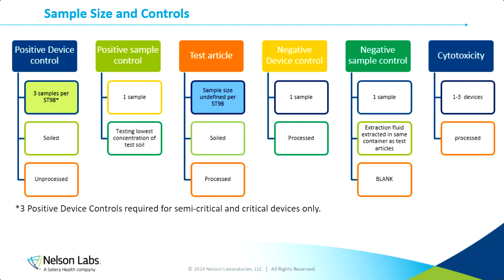The next topic or change is surrounding sample size and controls. These are all the necessary controls of a cleaning validation. We have the positive device control, and in ST98 they want to see 3 samples used for this. That would be 3 devices that get soiled and do not get processed. They just get extracted, and an exhaustive extraction efficiency is typically required and performed. The next control is the positive sample control. This is a sample where we spike our extract fluid with the test soil, testing the lowest concentration.